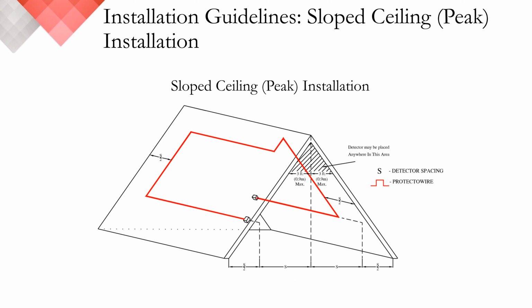In a peak slope ceiling, similar to a shed ceiling, a row of detectors is required within 3 feet of the high side of the ceiling. Spacing then will follow the requirements for spacing of that ceiling type. Spacing shall be based on the horizontal projection of the ceiling, and for ceilings with less than 30 degrees slope, use the ceiling height of the peak for spacing. For greater than 30-degree slope, use the average slope height, except for those at the peak.